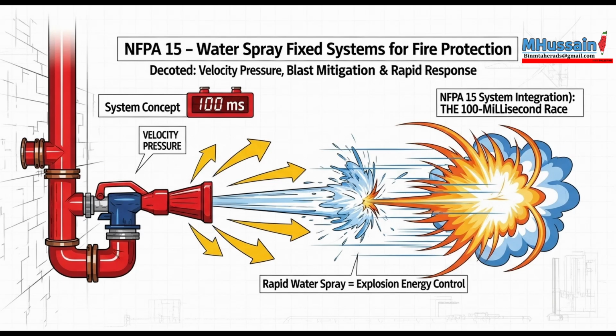During the discharge test, the main system control valve has to be partially closed, throttled down, until the pressure gauge reading at the hydraulically most remote nozzle exactly matches the minimum required nozzle pressure that came out of the engineer's hydraulic calculations. Wait, you're deliberately reducing the system's performance during the test. Why on earth would you do that? Because you're not testing maximum flow capacity here. You are testing the accuracy of the hydraulic calculation.